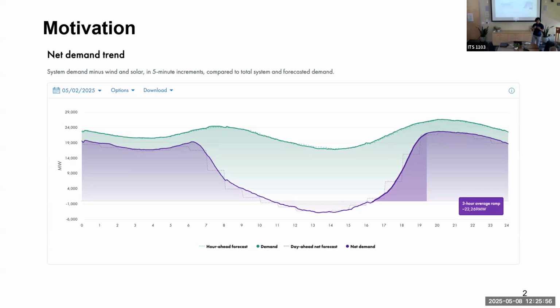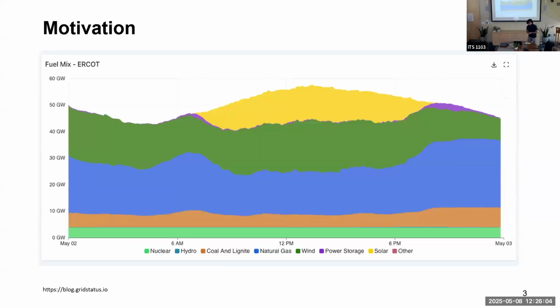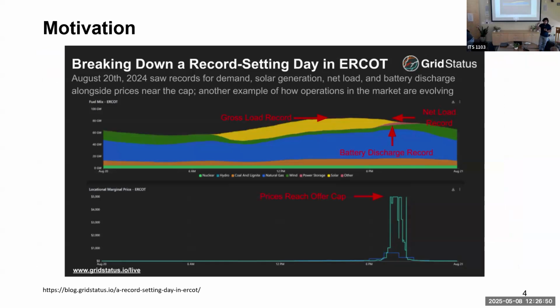So the solar duck curve has created some challenges for grid operation on a day-to-day basis. And if we go beyond just California, this is ERCOT, and the values on the left suggest that they have around 3 times as much load as CAISO has. This is a comparative day on May 2nd. Even here, after 6 p.m. when the solar is going down, they're ramping up their natural gas and they're ramping up their coal. So it's not only happening in California, it's going beyond our borders now. And as more and more solar gets installed throughout the country and the world, this problem is only getting worse with each jurisdiction.